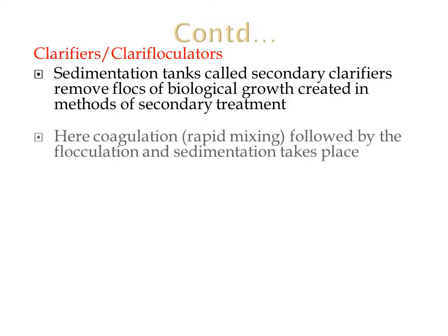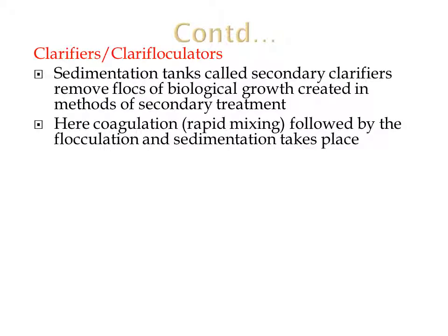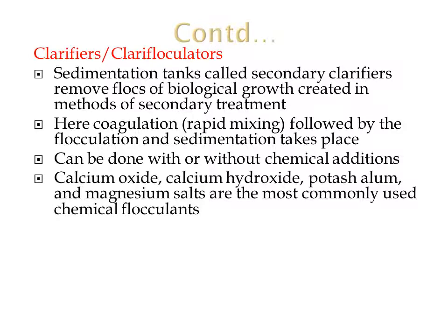Clarifiers or clariflocculators. After carrying out the biological treatment, sedimentation tanks called secondary clarifiers are used, and these clarifiers remove the flocs of bacterial growth. Here coagulation takes place, followed by flocculation and sedimentation, and this clarification can be done with or without the use of chemical additions. When chemicals are used, some examples are calcium oxide, calcium hydroxide, potash alum, and magnesium salts.